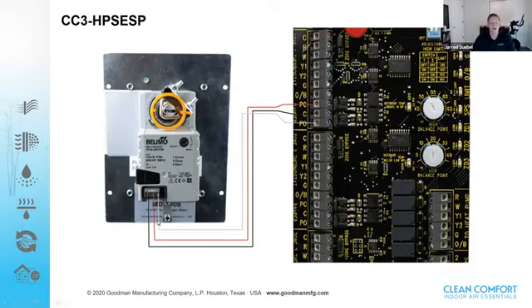However, a 3-wire actuator does not require nearly as much power as a 2-wire actuator does. The reason is the actual physics of the motor. I explain it like, imagine a digital or analog clock versus a wind-up clock. A 3-wire motor is what we call a 2-position floating point actuator, which means we power it closed or power it open. So we can turn and manipulate that motor to stop those damper blades wherever we would like.